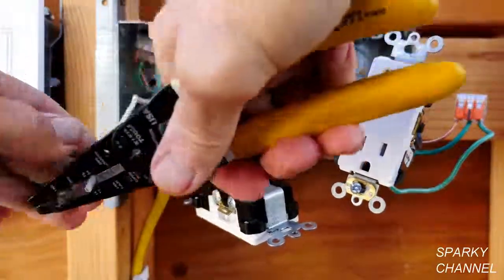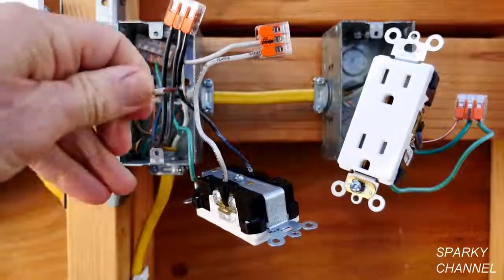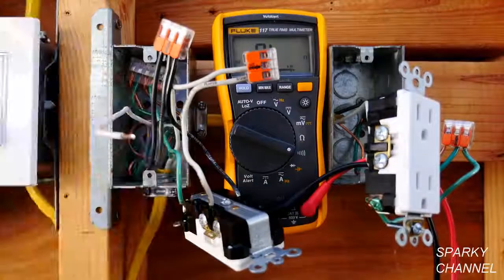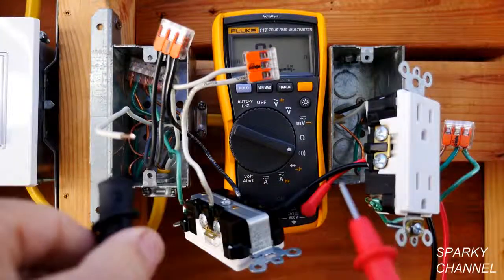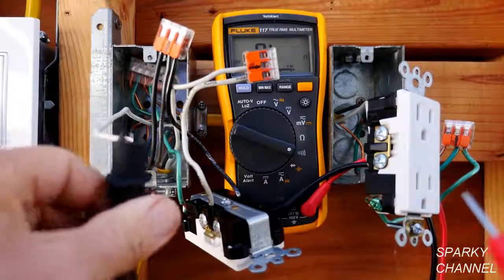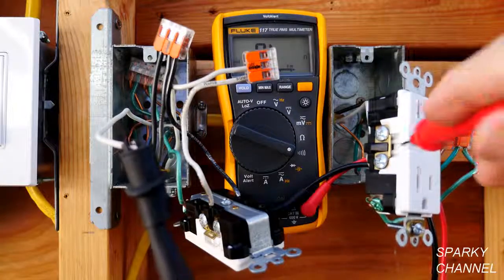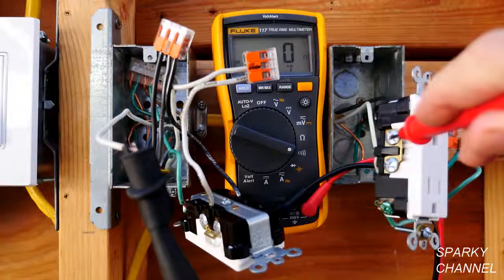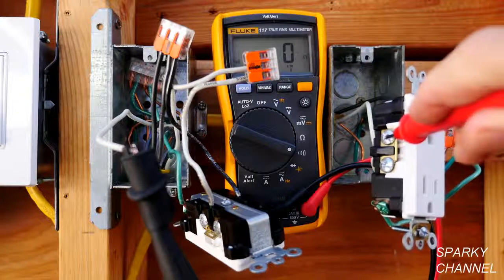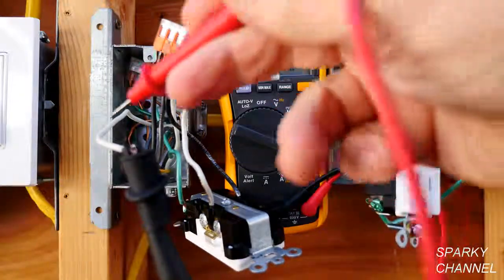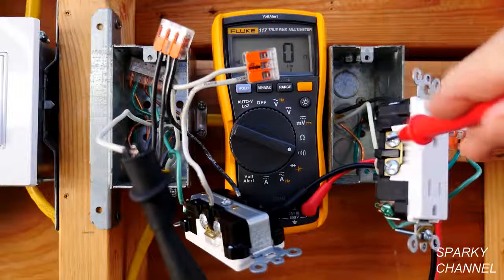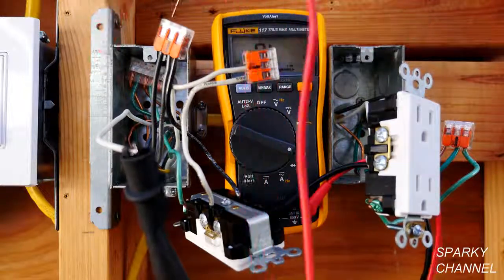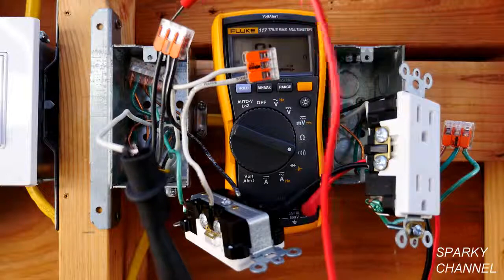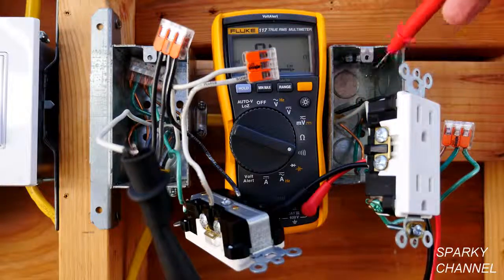So what I'm going to do is go ahead and strip off a little bit of the wire, and with my meter on continuity and of course the electricity off, I'm going to put one lead on the white wire and one lead right here on the silver terminal. We find they are continuous. So this is the neutral wire in question right here. This is the neutral wire that travels from this upstream box to this end of the run box right here.